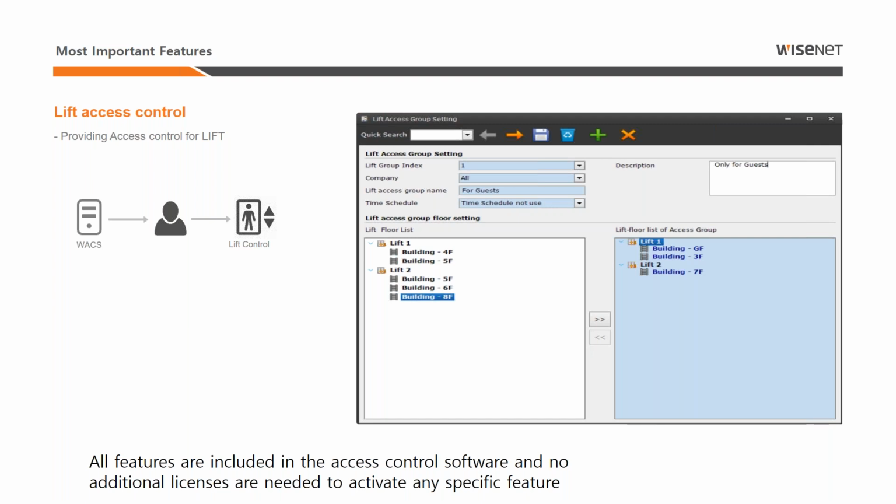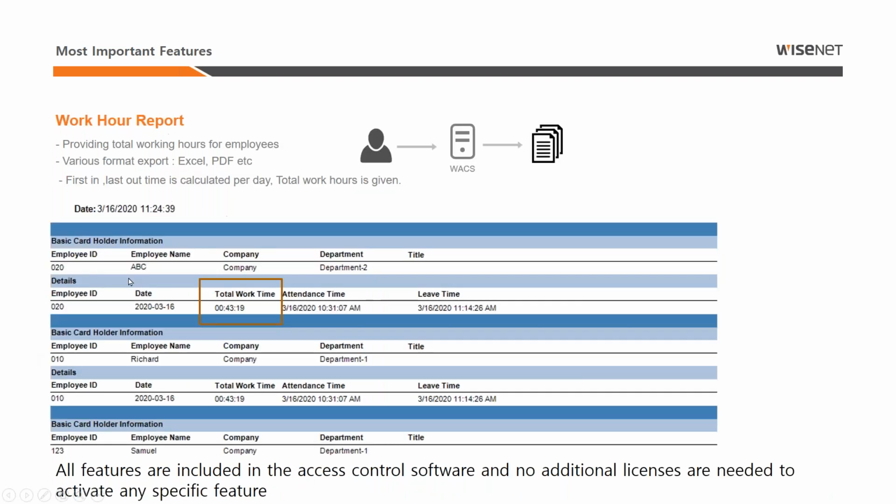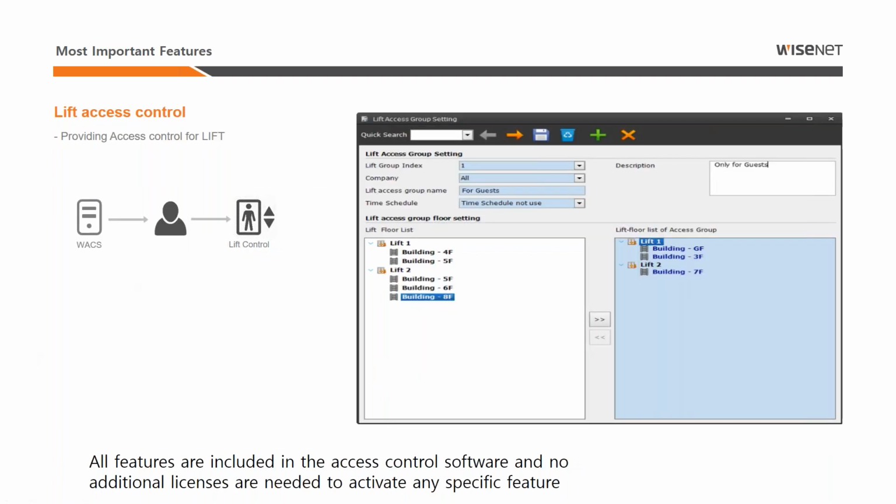You can create a lift. Every floor you can assign a relay, and then based on your user rights, only those relays will open. So if I have access to lift 1 and 2, and I have access to only the 20th floor, that means whenever I go to lift 1, I swipe, only the 20th floor will be allowed to press. The other floors, even if I press, it will not open. Got it? So we have relay boards called output boards for every floor. You can assign one relay contact.